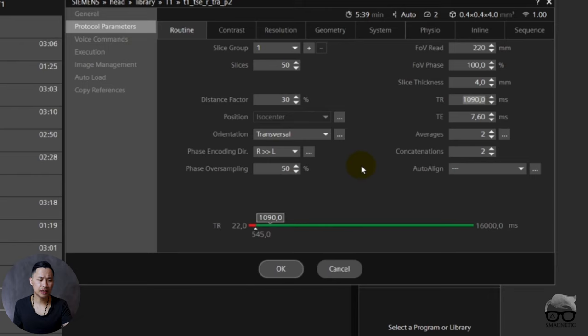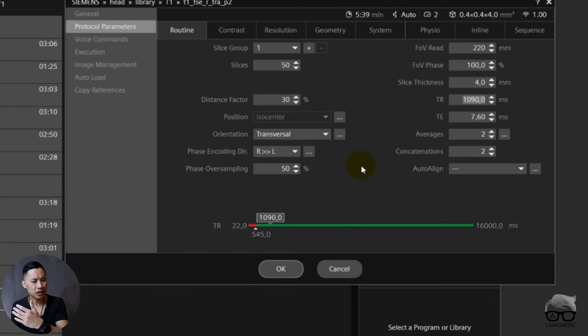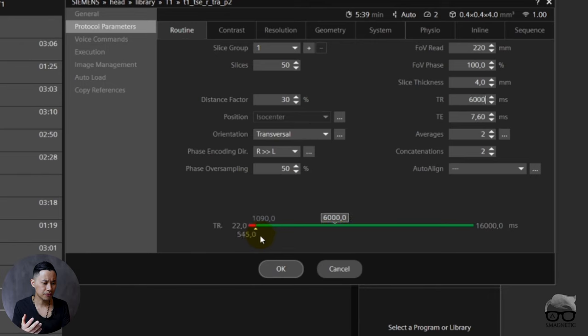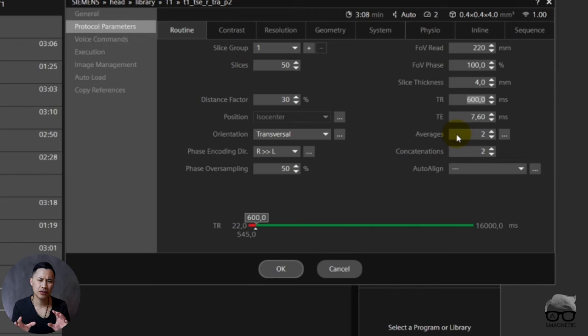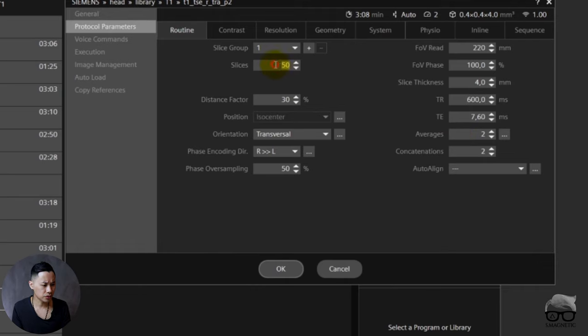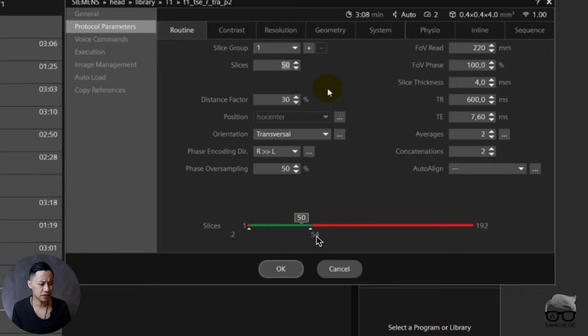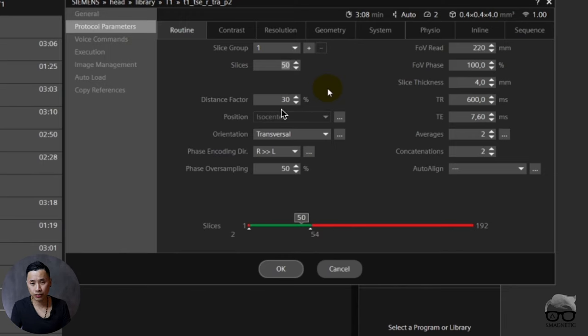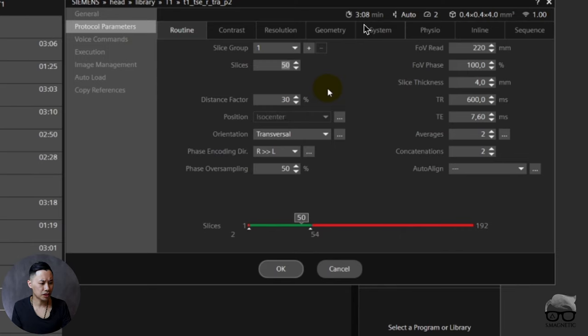But with two concats it means that I can have 100 slices, right? Double up. But instead of using more slices, because I'm happy with 50 slices, I can now lower the TR. If you lower the TR now, you will save the scan time from five minutes and 40 to around three minutes. So I'm still around, let's say in this case 600. So I lowered the scan time again. I'm utilizing almost all these nice slices I got available, like four more slices available, but let's say I just want 50. And you can see here you can have 30% or zero without the crosstalk. You now have almost the same scan time but more coverage.